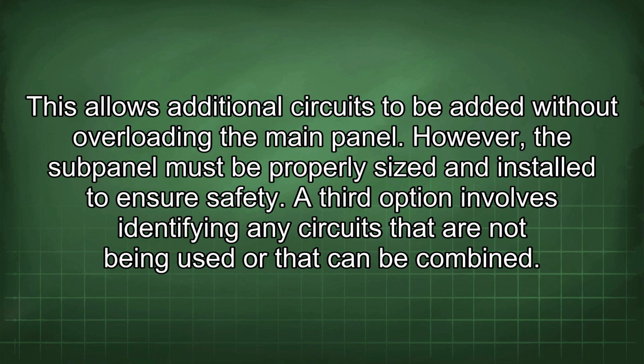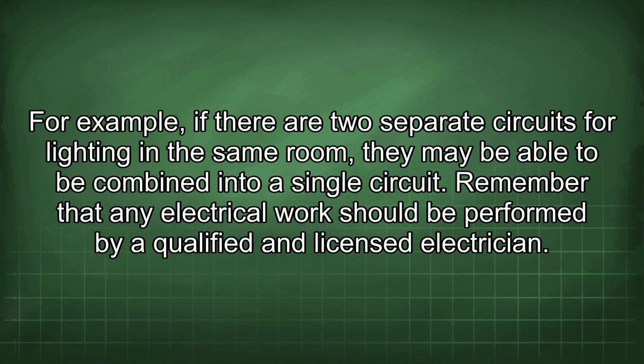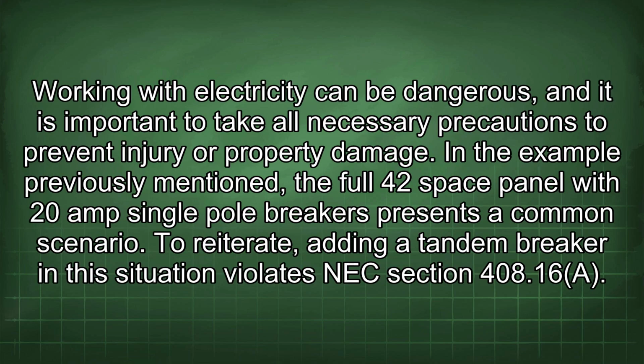A third option involves identifying any circuits that are not being used or that can be combined. For example, if there are two separate circuits for lighting in the same room, they may be able to be combined into a single circuit. Remember that any electrical work should be performed by a qualified and licensed electrician. Working with electricity can be dangerous, and it is important to take all necessary precautions to prevent injury or property damage. In the example previously mentioned, the full 42 space panel with 20 amp single pole breakers presents a common scenario. To reiterate, adding a tandem breaker in this situation violates NEC section 408.16(A).